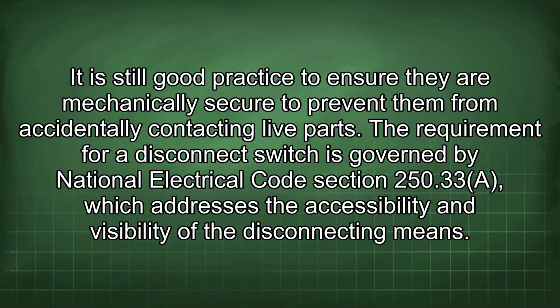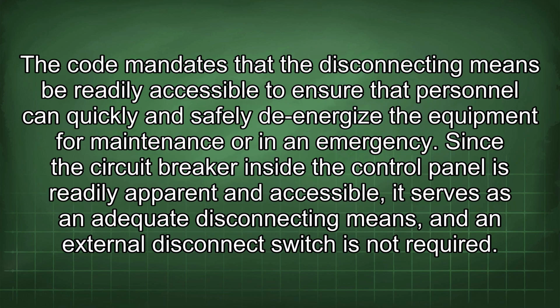contacting live parts. The requirement for a disconnect switch is governed by National Electrical Code Section 250.33a, which addresses the accessibility and visibility of the disconnecting means. The code mandates that the disconnecting means be readily accessible to ensure that personnel can quickly and safely de-energize the equipment for maintenance or in an emergency. Since the circuit breaker inside the control panel is readily apparent and accessible, it serves as an adequate disconnecting means, and an external disconnect switch is not required.